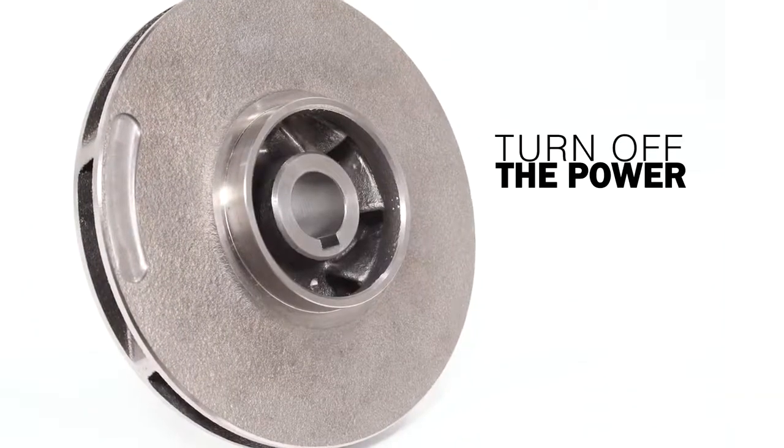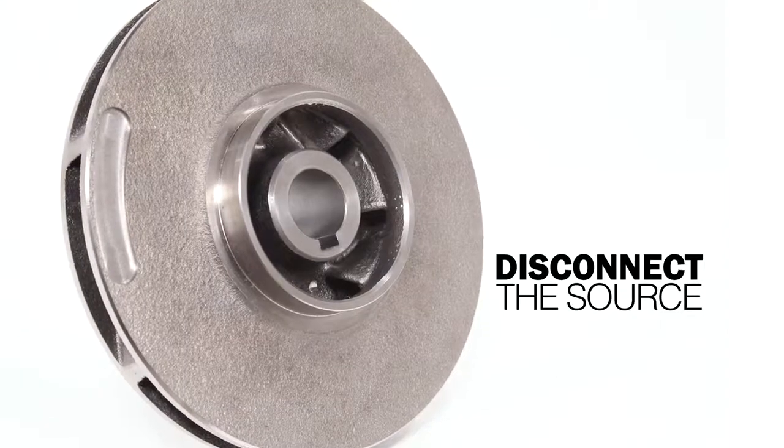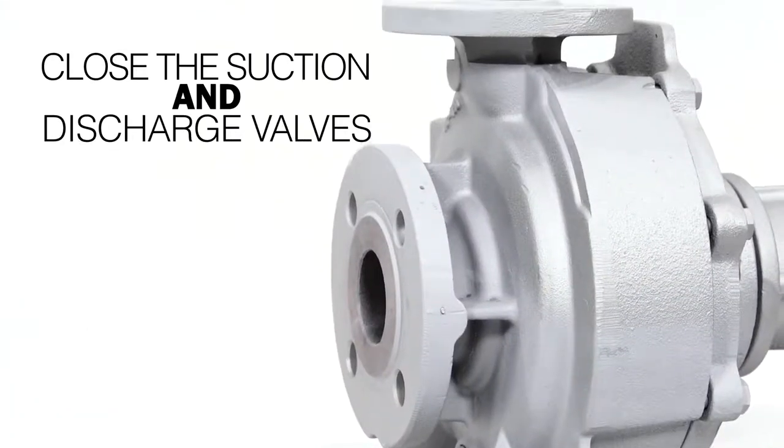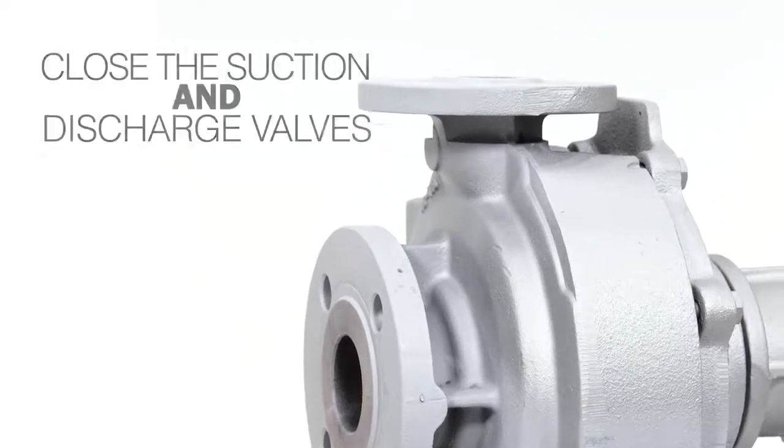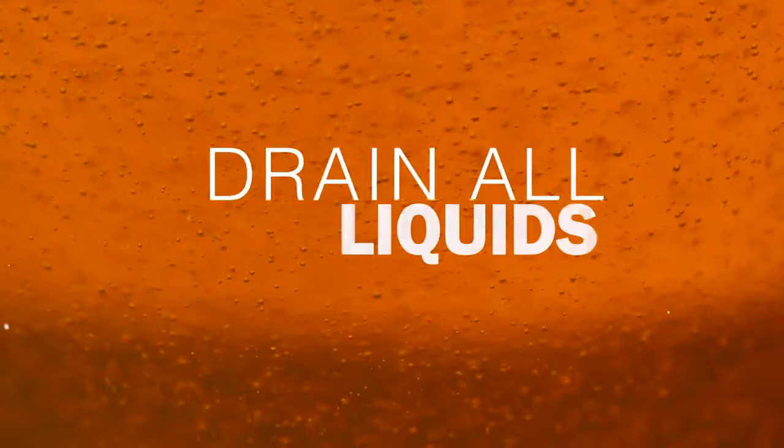If the pump is installed, turn off the power and disconnect the power source. Close the suction and discharge valves to isolate the pump from the liquid media. Drain all liquid from the pump.